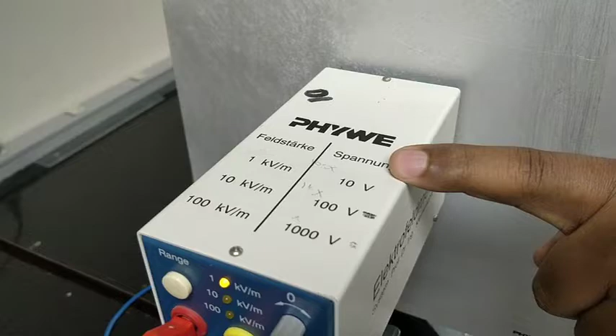Electric field is in volts per meter, and the conversion between the voltage you measure using these two terminals will be equivalent to a given value of electric field, as given here. So every 1 kilovolt per meter will be equal to 10 volts, if you are using the first range.